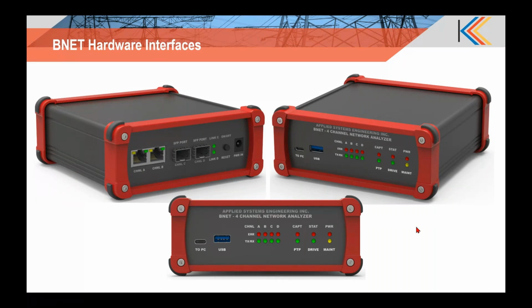A question I received quite frequently at a recent conference I attended is: is BNET expensive compared to the standard test set price? Actually, no. If you look at the price of other process bus products in the market, BNET is much less. We want all technicians to have the capability to analyze the process bus because if we switch to the 61850 digital substations, then most of the analysis and troubleshooting that you do in the DNP3 substations will have to be done on 6150 as well, right?